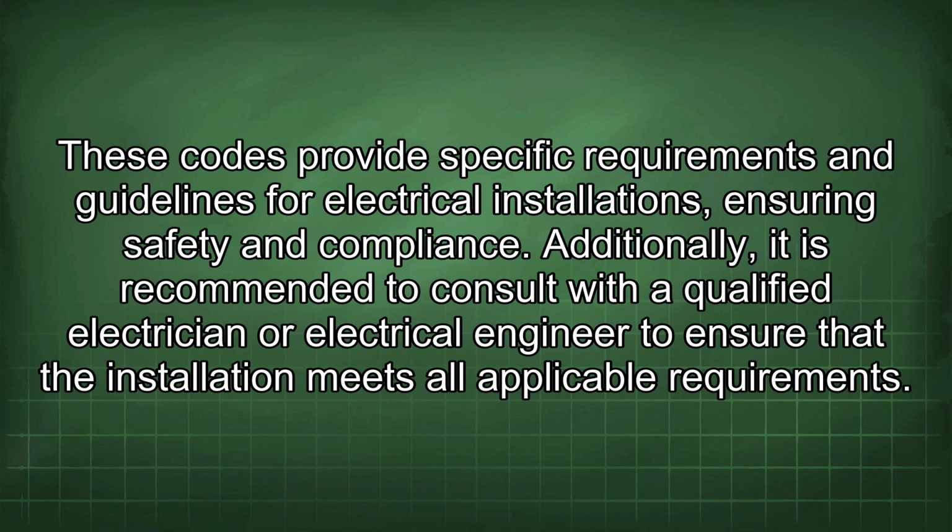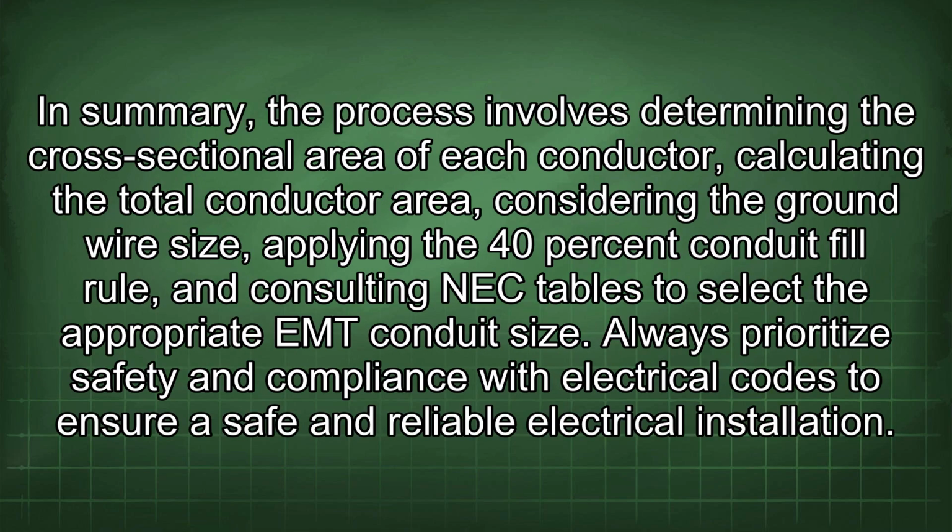Additionally, it is recommended to consult with a qualified electrician or electrical engineer to ensure that the installation meets all applicable requirements. In summary, the process involves determining the cross-sectional area of each conductor, calculating the total conductor area, considering the ground wire size, applying the 40% conduit fill rule, and consulting NEC tables to select the appropriate EMT conduit size. Always prioritize safety and compliance with electrical codes to ensure safe and reliable electrical installation.